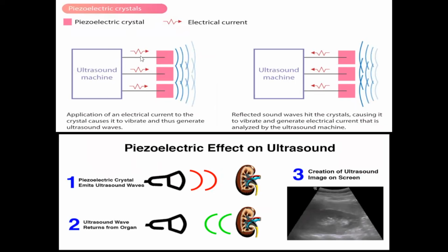Look at it. In your ultrasound machine, the electrical signal comes, your piezoelectric crystals vibrate and produce ultrasonic waves, and they echo back. This is your reflected sound wave, which comes back to the piezoelectric crystal and is transmitted to your ultrasound machine. So the piezoelectric crystal emits ultrasound waves. The ultrasound wave returns from the organ, creating the ultrasound image on the screen. Application of an electrical current to the crystal causes it to vibrate, thus generating ultrasound waves. Reflected sound waves hit the crystals, causing them to vibrate and generate an electrical current that is analyzed by the ultrasound machine.